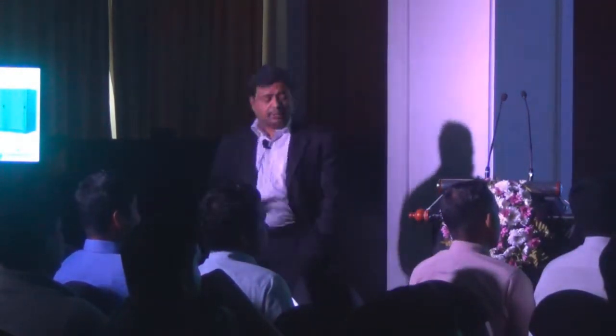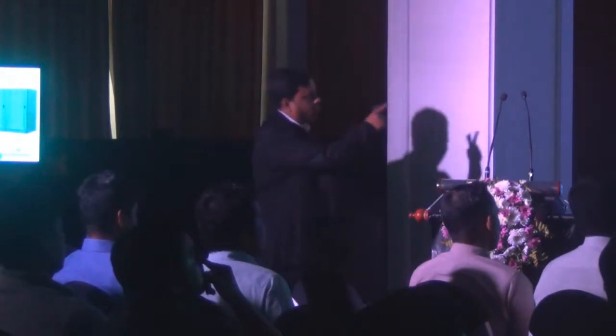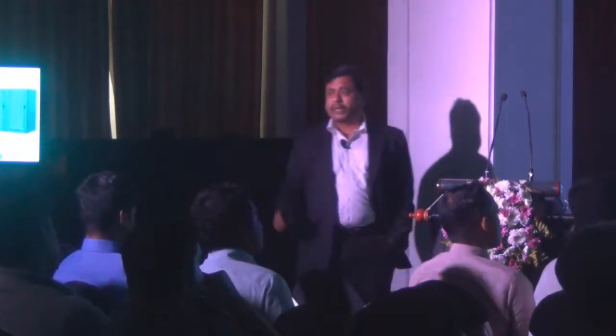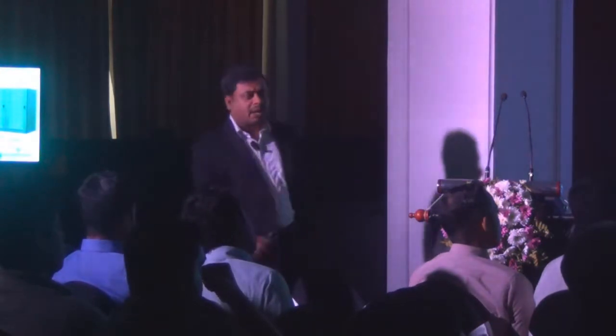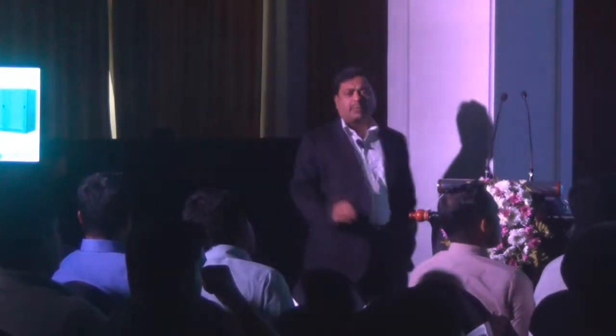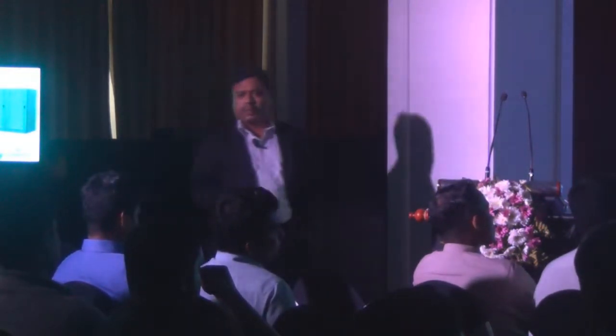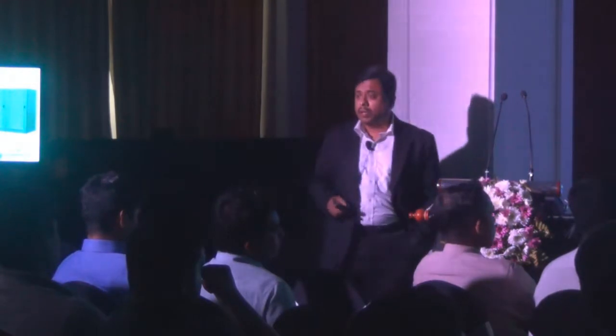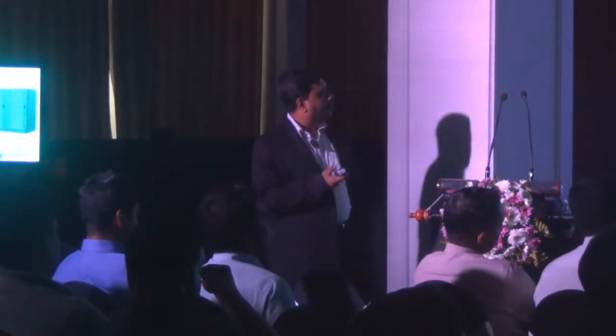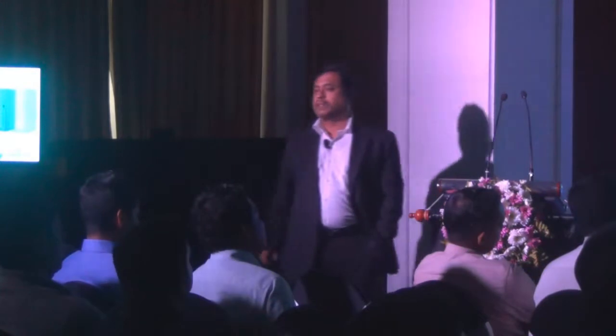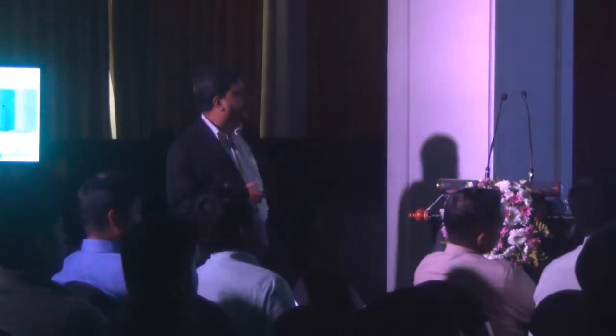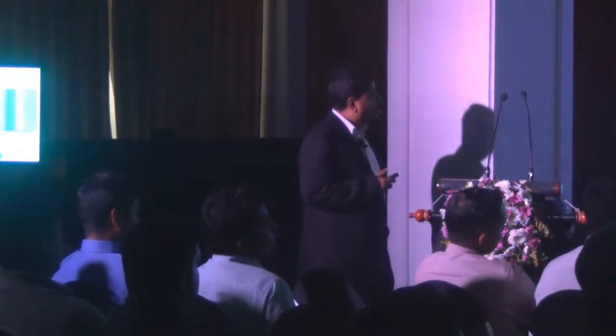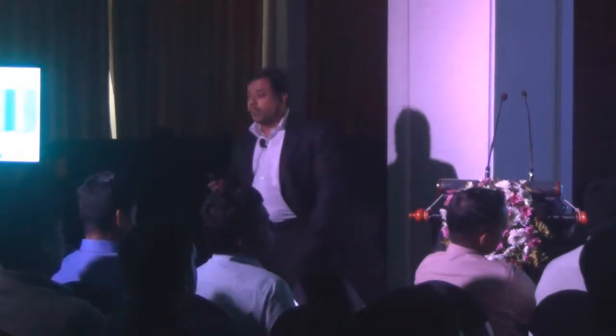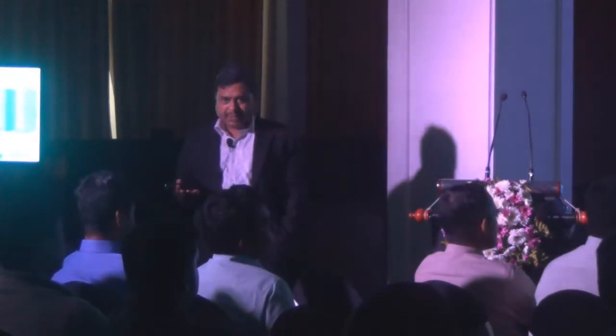So what it gives, on this particular slide, there are four 200 kilowatt modules with an IO box. So this is at 100% load. On a given point of time there may be 100% load, whether on weekdays or on a holiday or during a specific period. If your load drops to 75%, what exactly happens? One module will go to sleep mode. Similarly, if the load goes to 50%, the second module will go. The third goes at 25%. That means one module will be working basically.